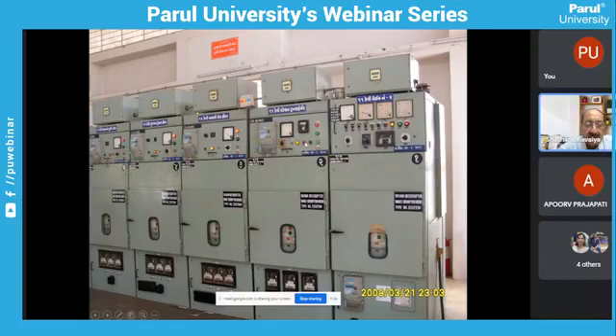Station transformer means from this particular panel, the feeder goes to an 11 kV transformer. From 11 kV, there is a step down to 415 volt. From that, this particular substation gets supply. So the lighting of this control room, switchyard lighting, and the pumps in the substation, everything gets power from this 11 kV station transformer. And this is an incomer, incomer number two. So every substation has at least a minimum of two 11 kV main incomers.